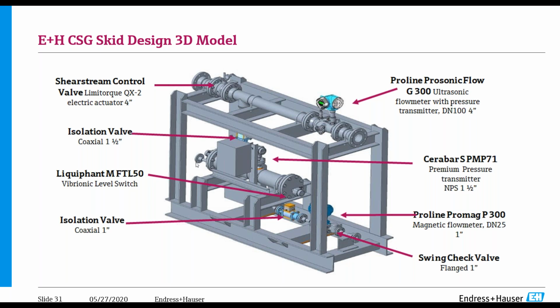So you'll see there's a 1-inch, on this particular diagram, coaxial solenoid valve, but it's also available in a ball valve version as well. And you'll see there's one on the water outlet and there's one on the gas outlet. What the level switches will do is detect if there's water approaching the top of the separator, then it will shut off the valve going to the gas line, thereby ensuring that we don't get water carryover into the gas line. And the bottom Liquiphant level switch will be looking for gas. If it sees gas, then it will shut the water outlet valve, thereby ensuring that we don't get gas down the gas water line. And then what happens in the gathering network downstream is it actually gets vented off to atmosphere at high point vents, which obviously we don't want.